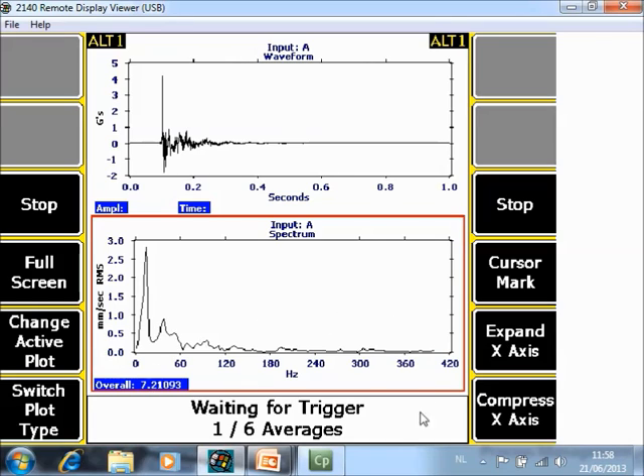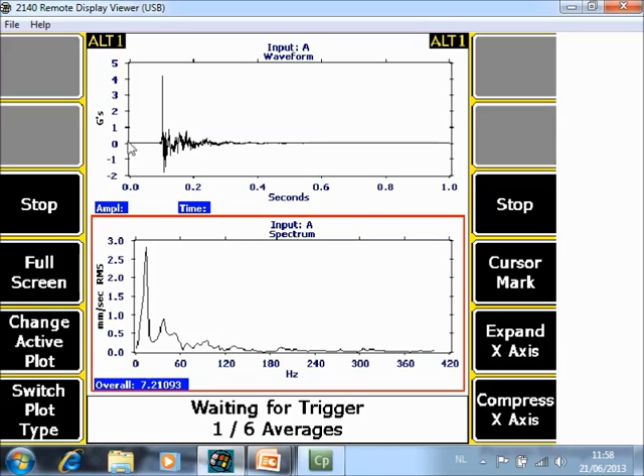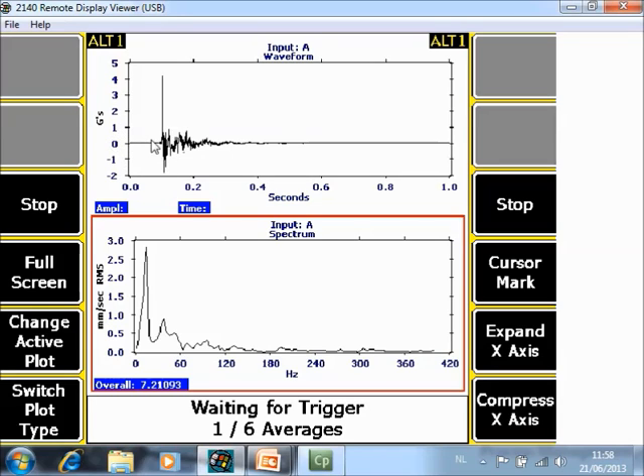Now he will average this 6 times, so he is waiting for the second impact. Before I continue, I am going to show you this part here. A part of the waveform that is stored is shown before the impacting level. That is called a pre-trigger percentage and that will be explained more in detail later on.